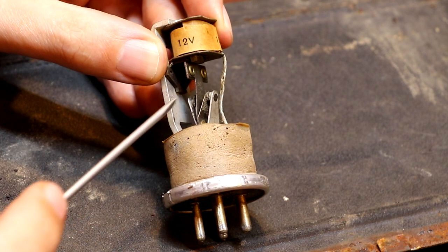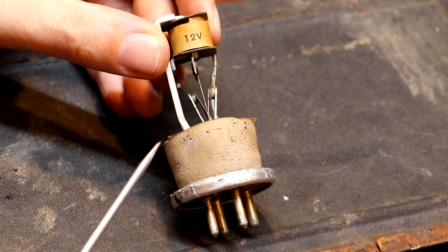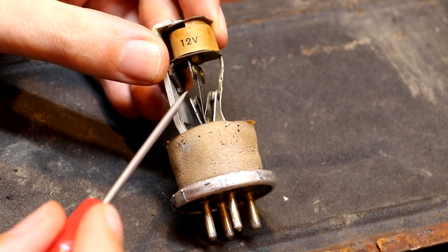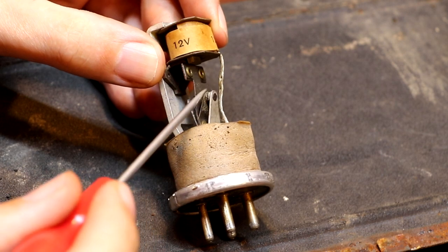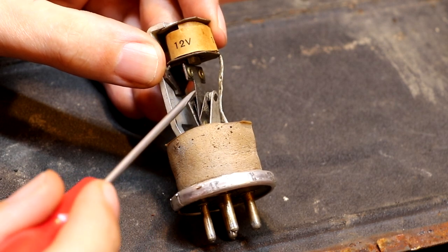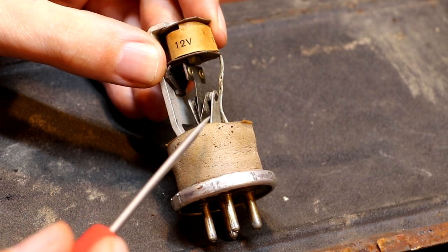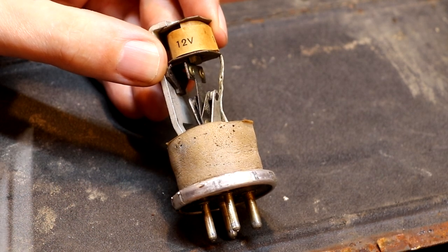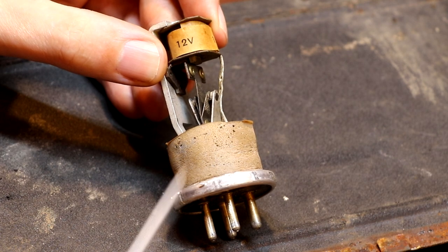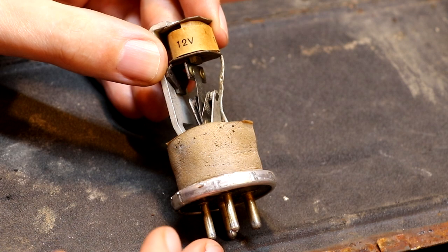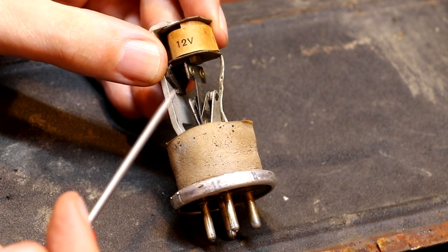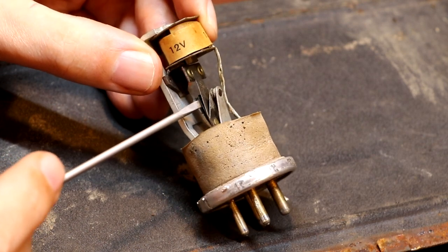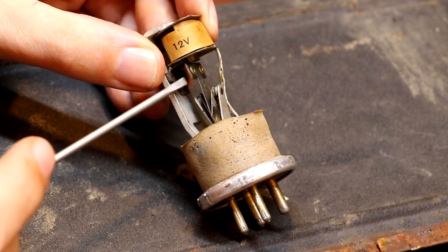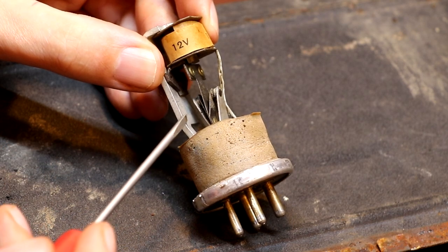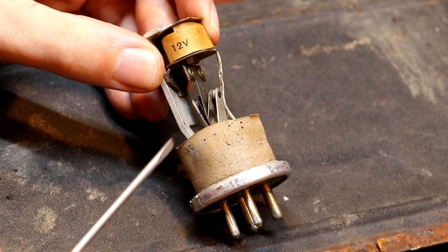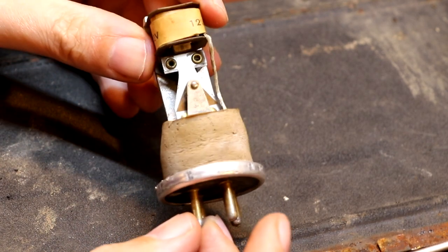But the problem with this one is the contacts are just burnt away, and although I've done my best to clean them and get it working again, it's very intermittent. Sometimes it works, sometimes it doesn't. You've got to try to clean the contacts, then bend them so they have just the right amount of pressure to do the switching they need to do. I can kind of get it to work - if you give it a bit of a tap, it'll start working, and then maybe it'll stop. But sometimes when you just put 12 volts on it, because this contact is bad, it doesn't always supply 12 volts to the coil to get it started. I've tried cleaning it and rubbing it with emery paper, but unfortunately it just doesn't seem to want to come good.